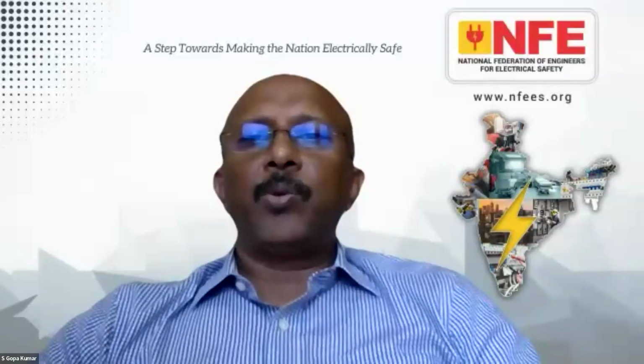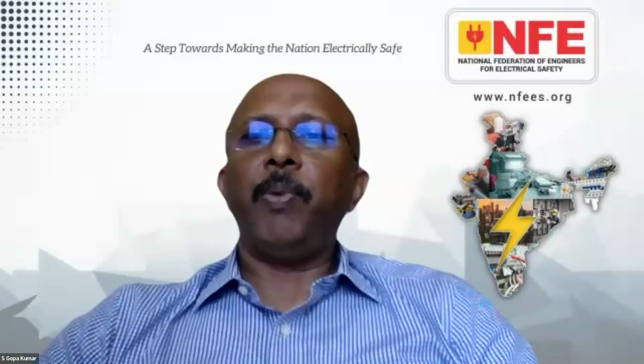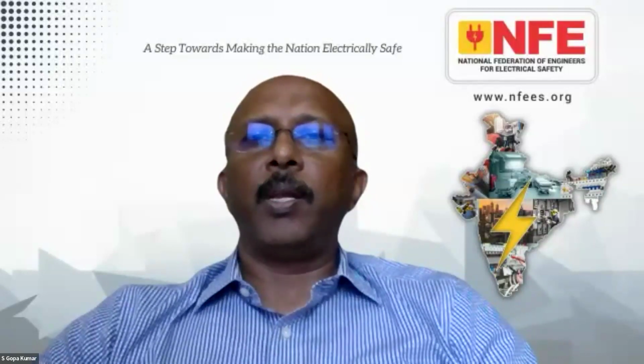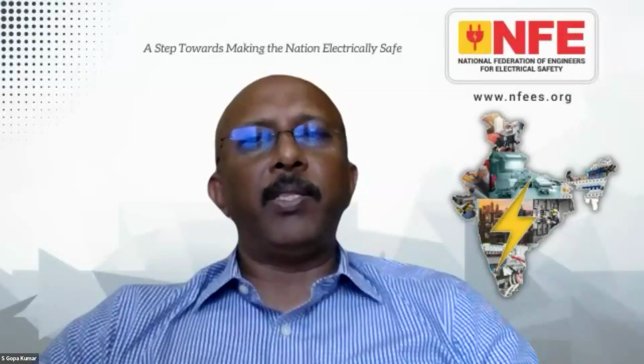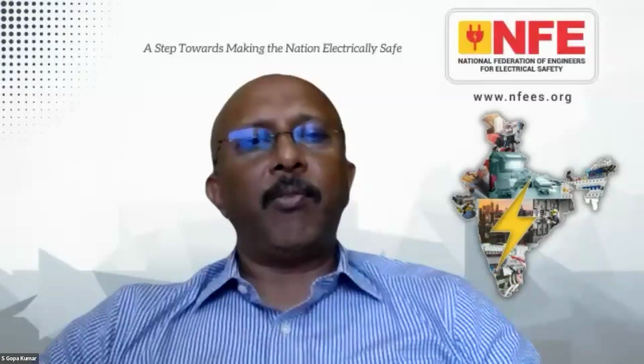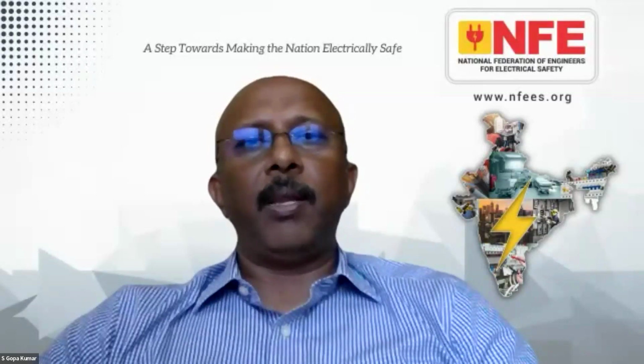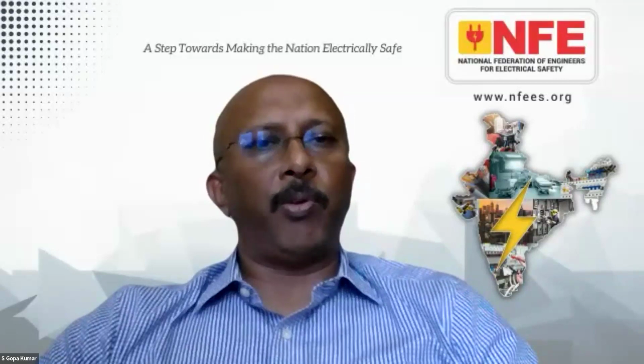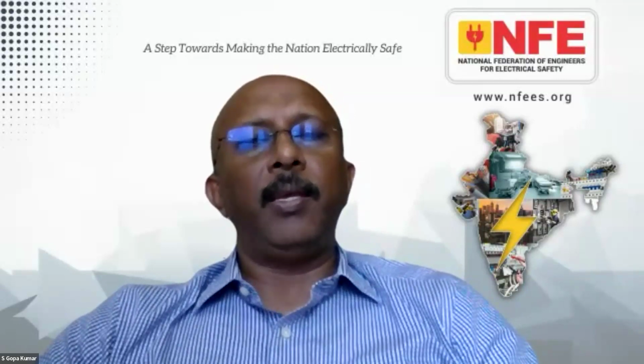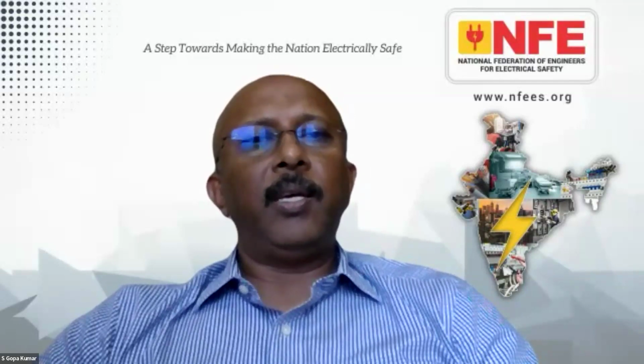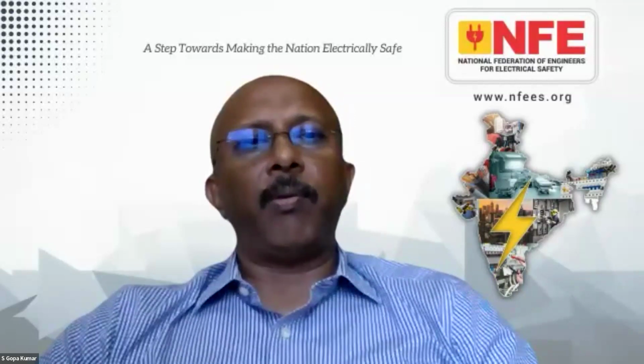Yeah. Thank you. So is it possible to measure loop impedance of PE/NE loops, from Mr. Ashok Suman? As per the standard, I understand that the loop impedance is tested between phase and earthing, and that is standard practice. That is called earth fault loop impedance, between line to earth. Of course, line to neutral can also be tested with the same meter. Line to line can also be tested, but neutral to earth is not possible because there is no voltage between N and E. This device needs the supply voltage to be applied for making the test.